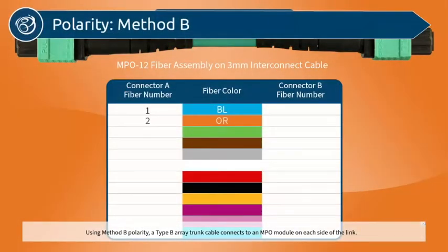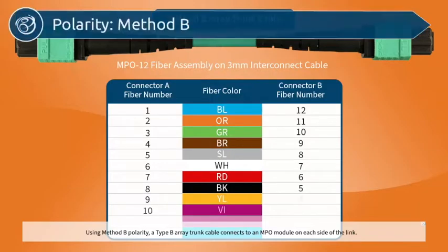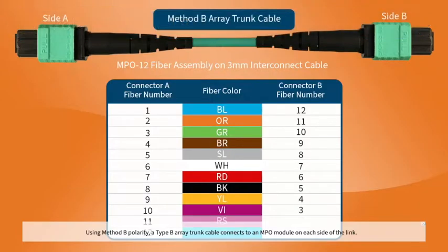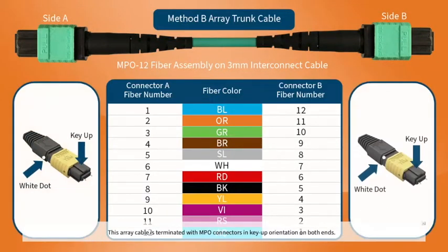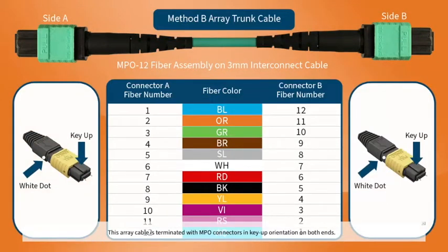Using method B polarity, a type B array trunk cable connects to an MPO module on each side of the link. This array cable is terminated with MPO connectors in key-up orientation on both ends.